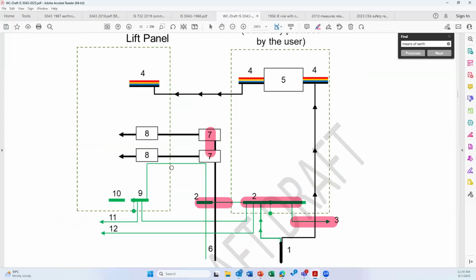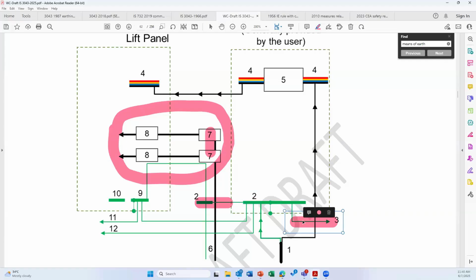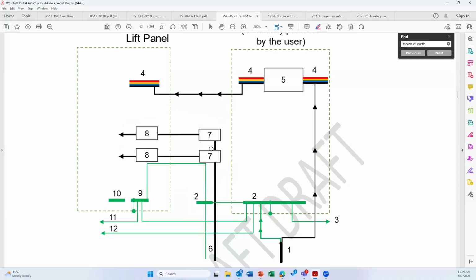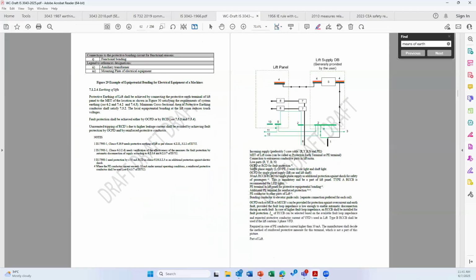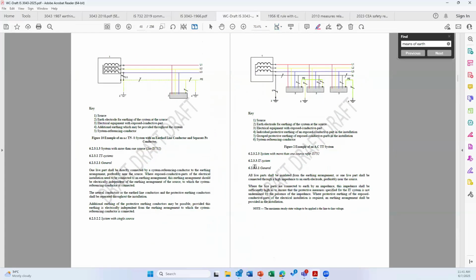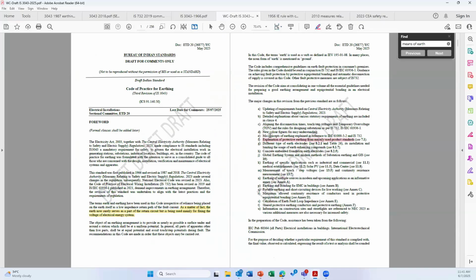In a TT system, sometimes you need to have an RCD for fault protection and an additional RCD, a 30 milliampere RCD, for the car. The single phase supply has to have a separate 30 milliampere RCD. That means in a lift, sometimes you may have to have a 300 or 500 milliampere RCD for the main power panel and a 30 milliampere RCD for the lift panel in order to protect people from electric shock. So this is information which has been included in the standard.